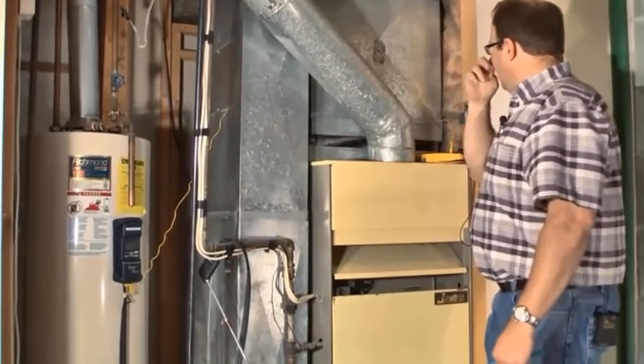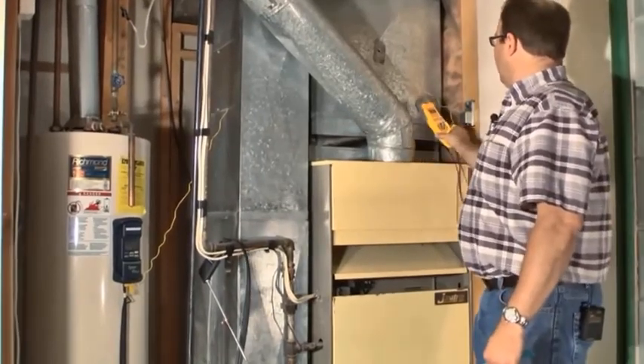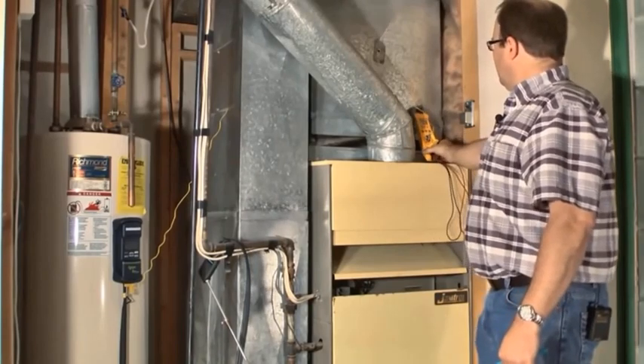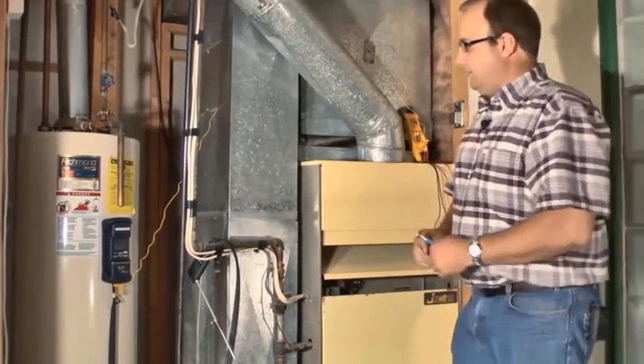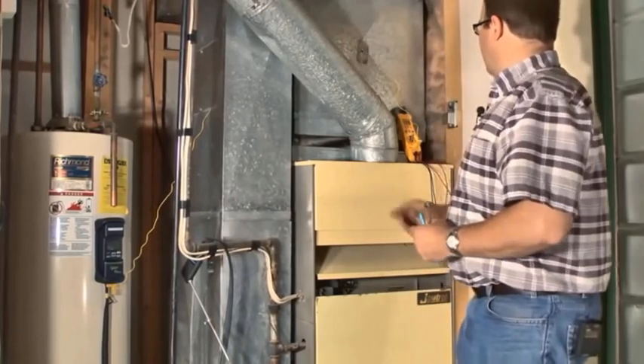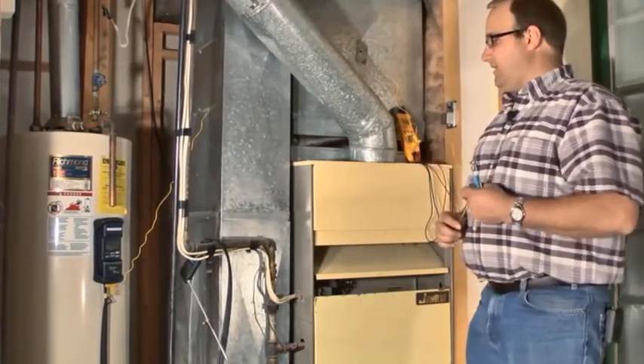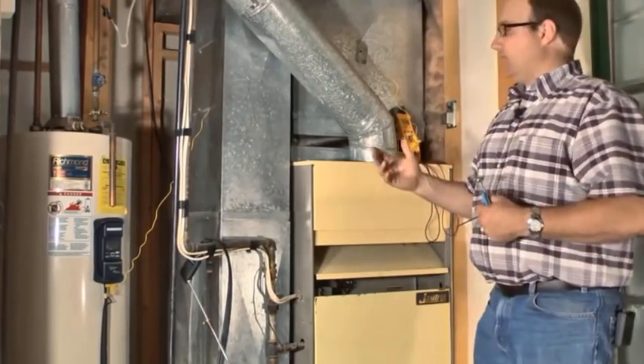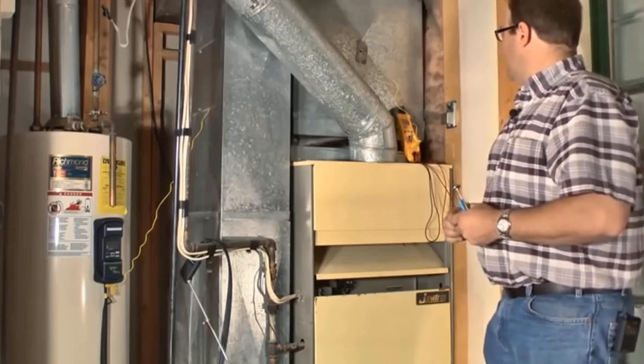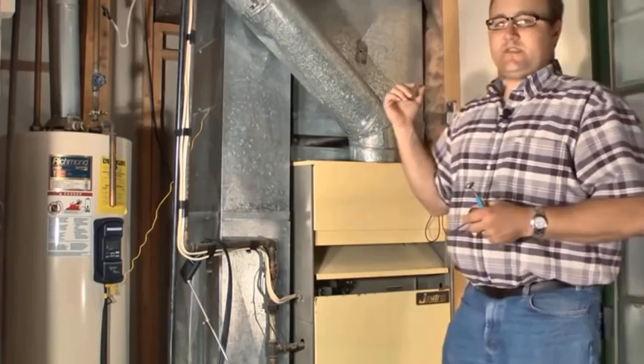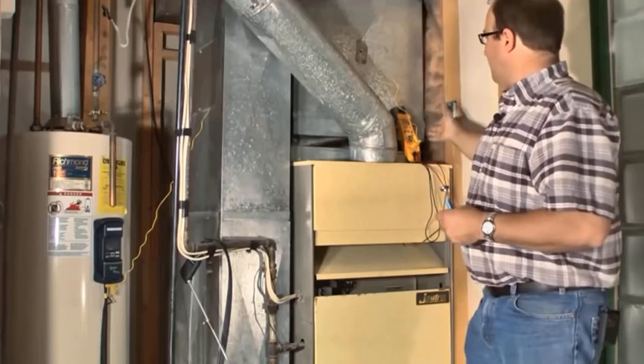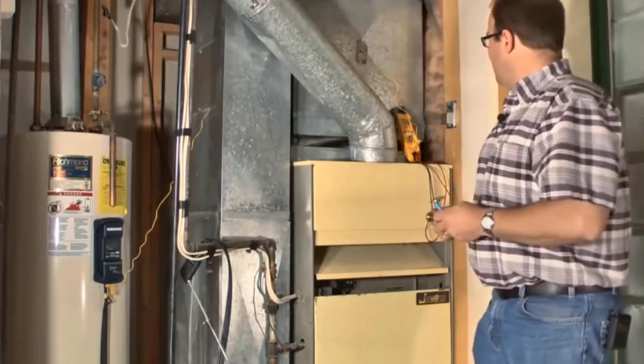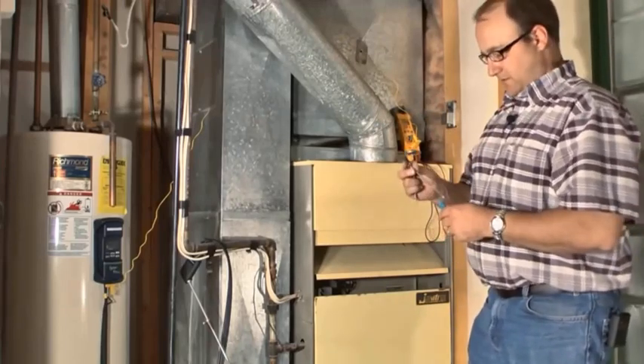I already turned the thermostat upstairs, so all I've got to do is turn the power on. And what we're going to watch for is the fan on temperature. So this thing will kick on here, and we'll get the fan on temperature at 5 minutes. We're going to be looking for our heat rise temperature, and then I have to go turn the thermostat down, and we want to get our fan off temperature.